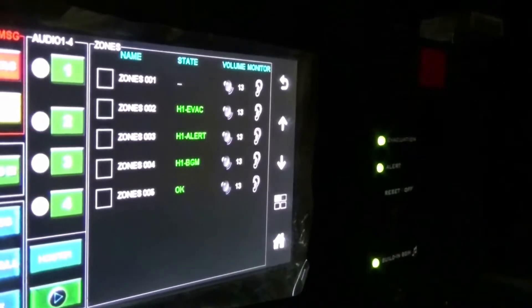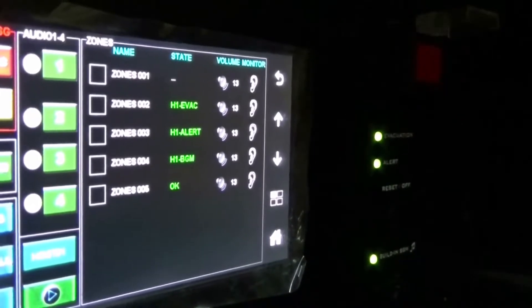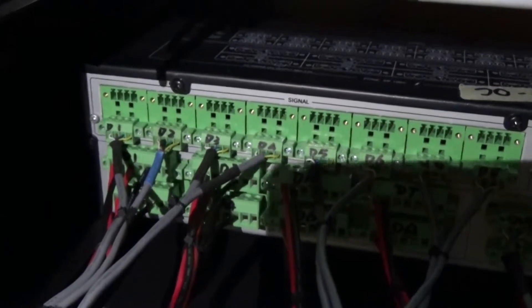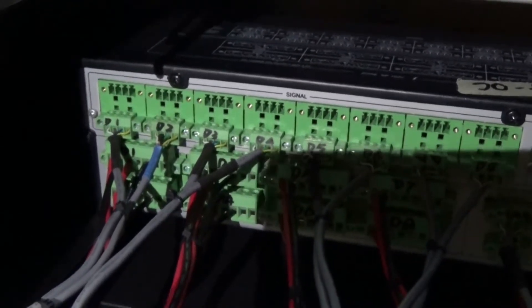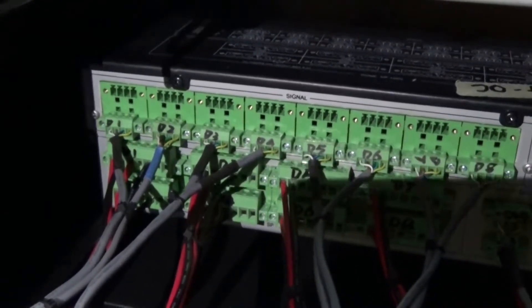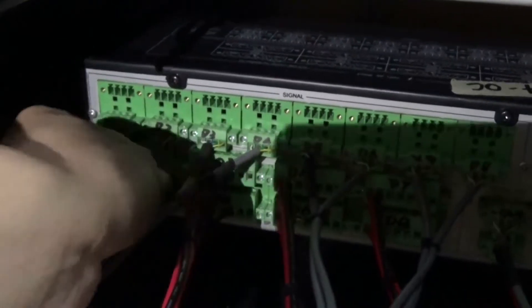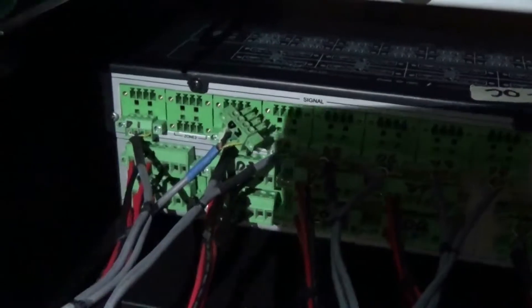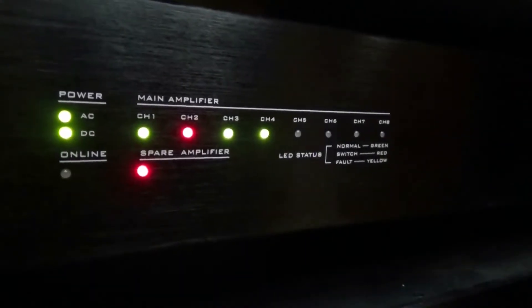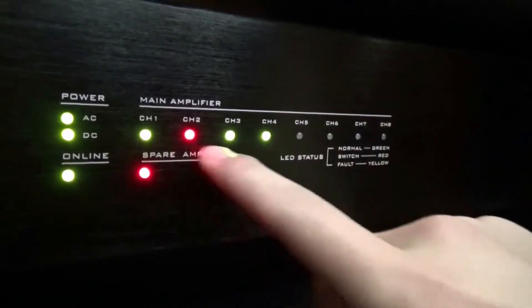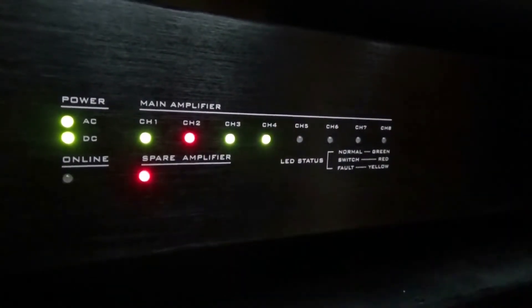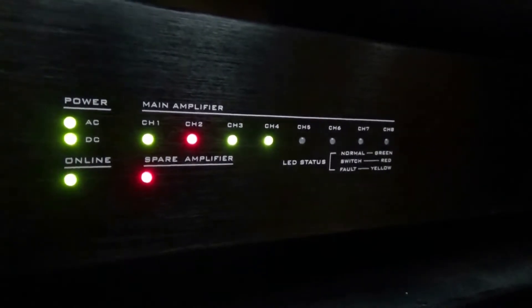Please wait for further instructions. May I have your attention please. This system can automatically detect all device working status. Now I'm going to cut off one of the amplifiers to simulate an amplifier problem. As you can see from the front panel, the amplifier changeover has activated the spare amplifier, so the sound is uninterrupted.